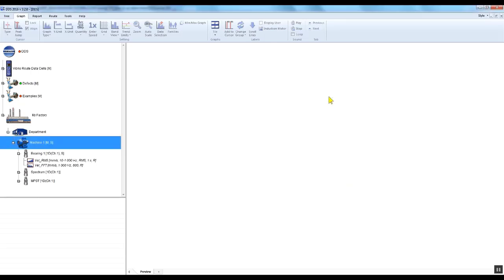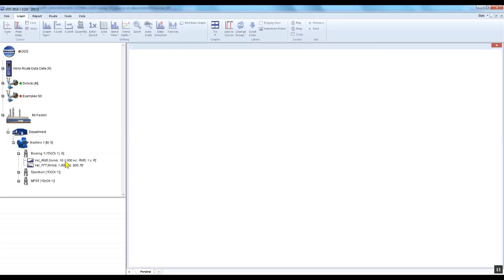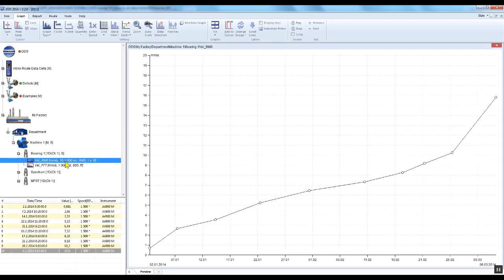However, the speed measured by the instrument has priority. For the Vibrio M, the speed will be taken from the first screen, auto speed detection or manual input. For the VA3 Pro or VA4 Pro, it is taken from the speed probe.